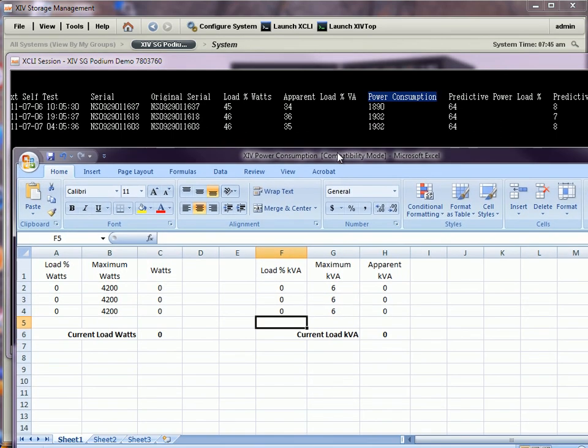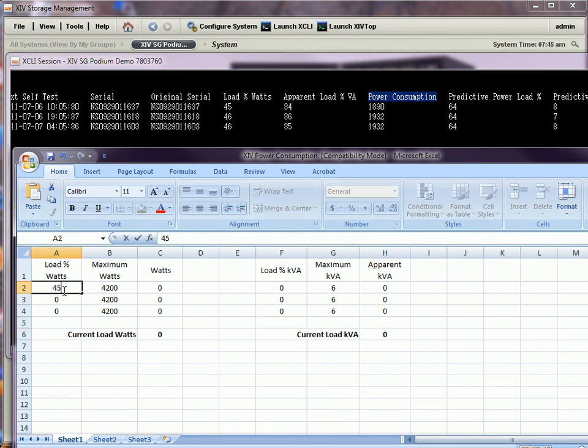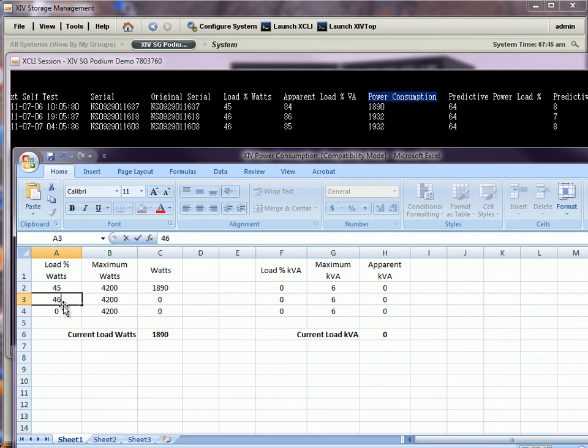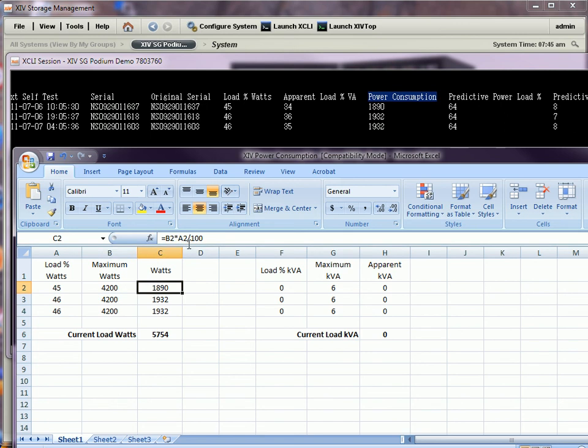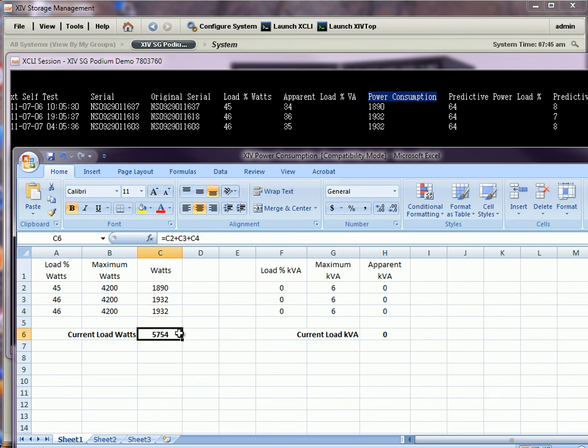What the spreadsheet tells me is that if I know the load percentage in watts, which is 45%, 46%, and 46%, and I know the maximum watts, which is currently 4200 for each of the three UPSs, then I can calculate the actual watts being used: 1890, 1932, and 1932, which totals 5754.